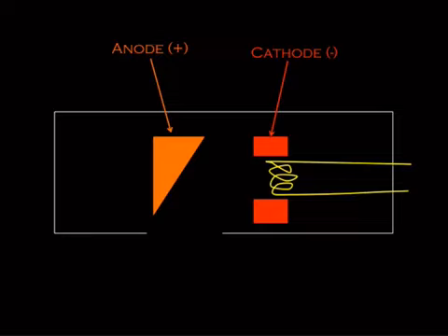Now the anode is also made of tungsten, just like the filament. And it's made out of tungsten because it has a very high Z, and that has to do with X-ray generation, which we'll talk about a little bit later. So we've got this system here, and we've got an electron. It gets pushed from the cathode to an anode, strikes the anode, and that generates one of these characteristic X-rays, among some other types of X-rays as well.